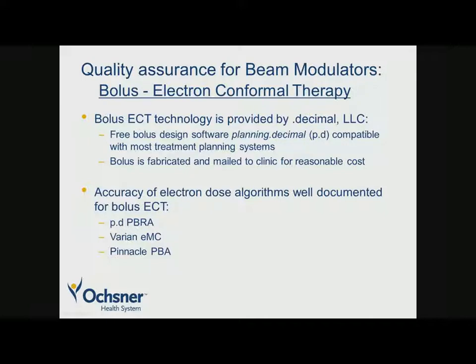Next is bolus electron conformal therapy. This is a relatively new process and not a lot of clinics are using it, but we were very active at Mary Bird Perkins and have done a couple of cases at Ochsner as well. Bolus ECT technology is provided by DotDecimal. There is free bolus design software — planning DotDecimal or P.D — compatible with most treatment planning systems, and the bolus is fabricated at DotDecimal after being designed at your facility, then mailed to the clinic quickly and at reasonable cost. A number of papers have validated the accuracy of dose algorithms for this approach, including the pencil beam redefinition algorithm used by P.D, which is a modification of Hogstrom's pencil beam algorithm used by Pinnacle, and Varian's electron Monte Carlo.